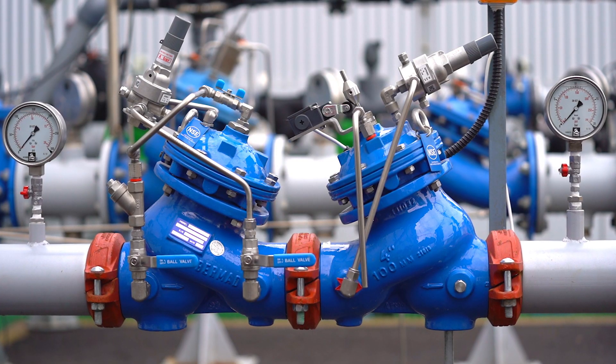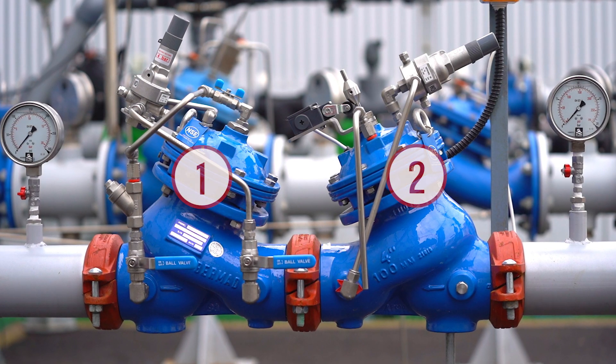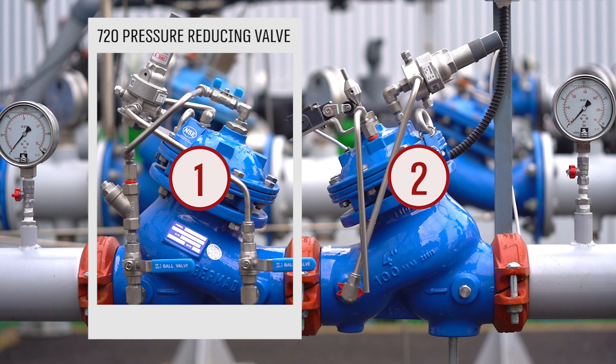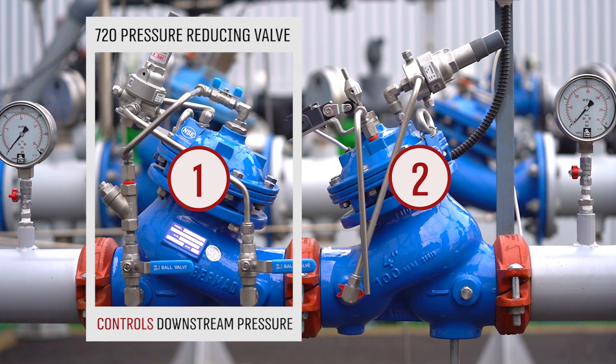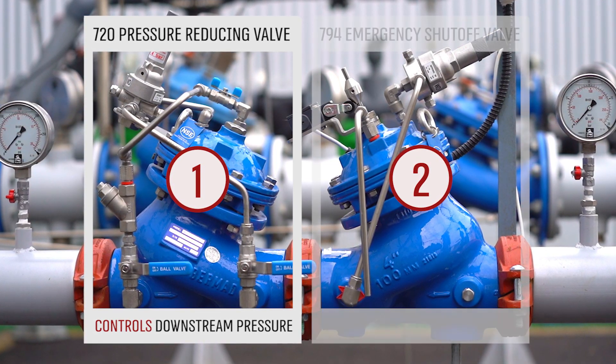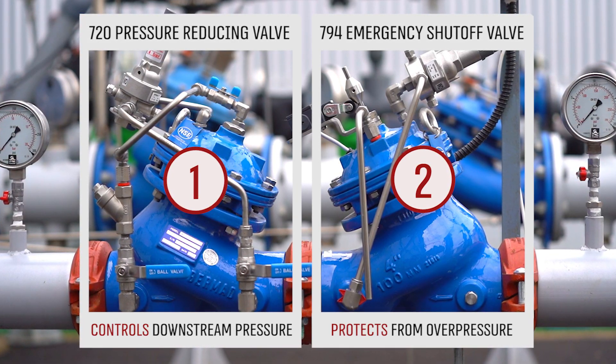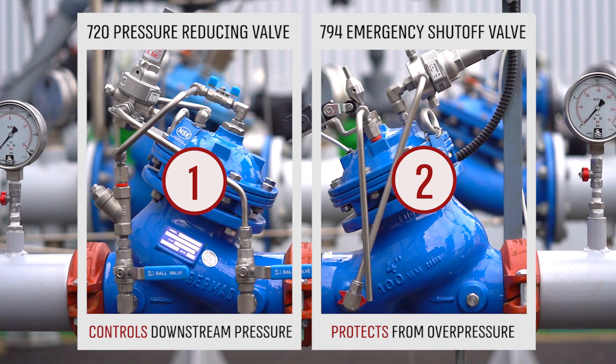This pressure-reducing station is designed to give extra security in the case where there is a possibility of damaging overpressure to the consumer pipeline. To accomplish that objective, the station incorporates two pilot-operated valves: the Bermad 720 pressure-reducing valve set to the required downstream pressure for the consumer line, and the Bermad 794 emergency shut-off valve set to a higher pressure value but below the maximum allowable level.